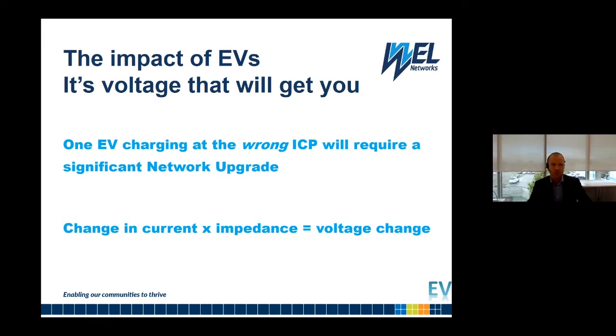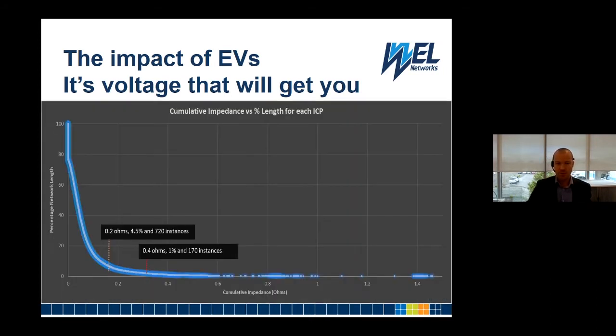Second point, in a very simplistic sense, a change in current multiplied by the impedance gives us a voltage change. So that brings us to our impedance curve, which shows the network to each ICP and the percentage of the network at that cumulative impedance.